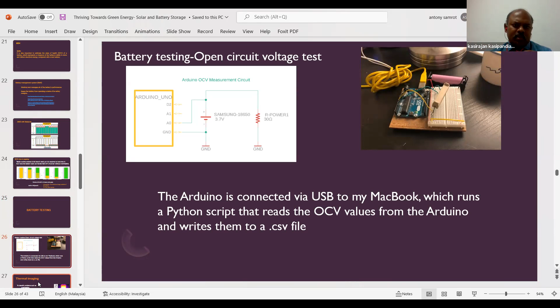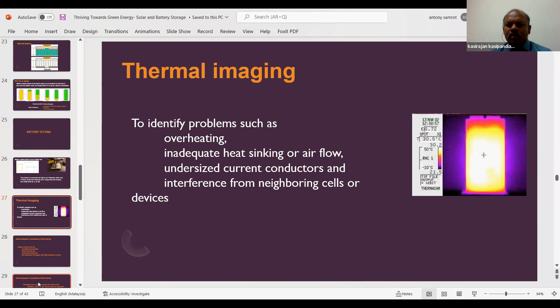Then thermal imaging, this is another type of test. From this test we can identify overheating, whether the battery is overheating or not, whether heat sinking is inadequate or sufficient, undersized current conductors, and interference from neighboring cells or devices. These are the different problems we can identify with the help of thermal imaging based on different color coding.